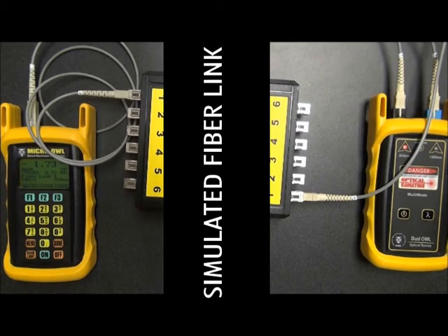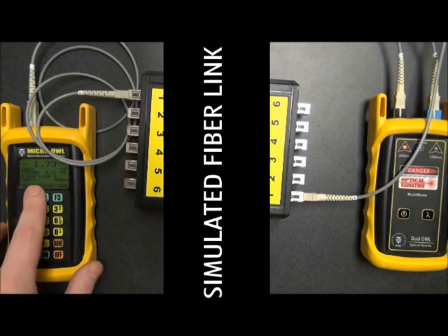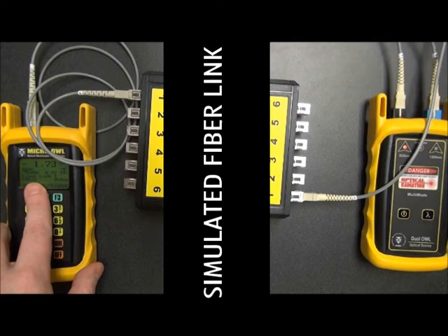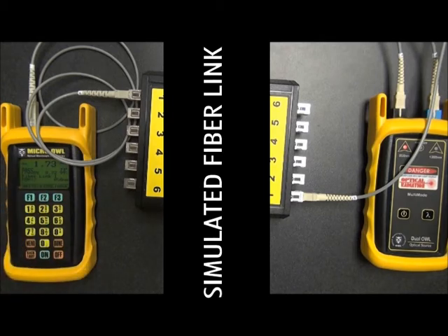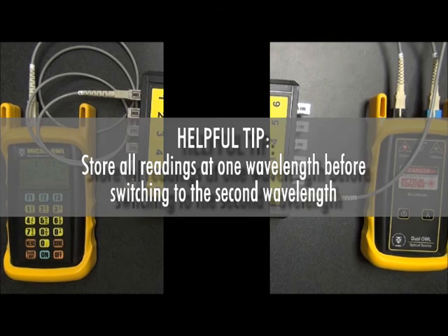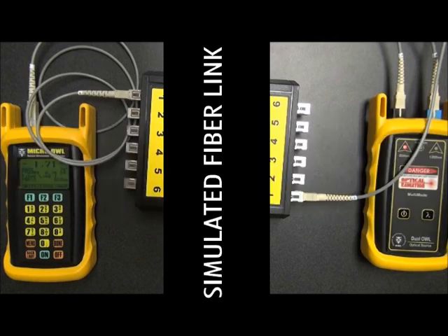Okay, now that we've saved fiber number 1, as you can see, the microOwl has already changed the number to 2. What it's doing is prompting you to hook into fiber number 2. Now, as a helpful tip, when storing readings with the dual OWL and micro OWL, the easiest way is to store all the readings at one wavelength first, and then switch the wavelength one time, and then store all 6 readings at the next wavelength.